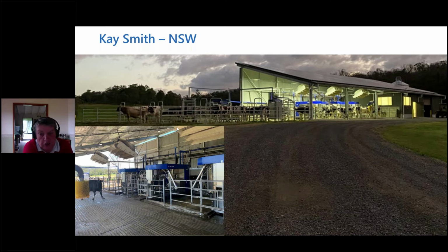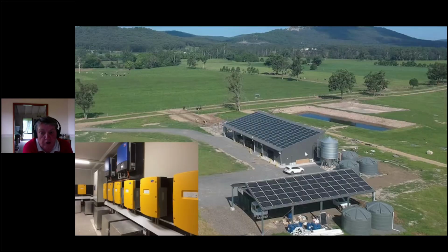It is set to come on when battery voltage gets down to 49 volts and cuts off when the voltage is up to 53. The generator can power the dairy and recharge the batteries at the same time. It is important to note that a generator would have been required even if the dairy was on grid, as the grid power is relatively unreliable, lots of downtime.